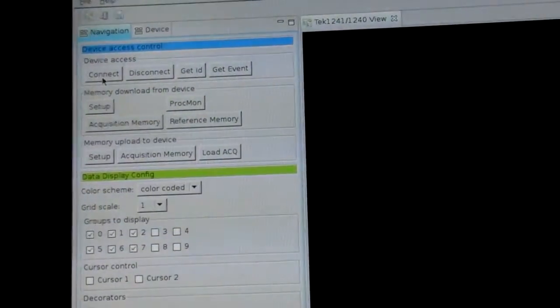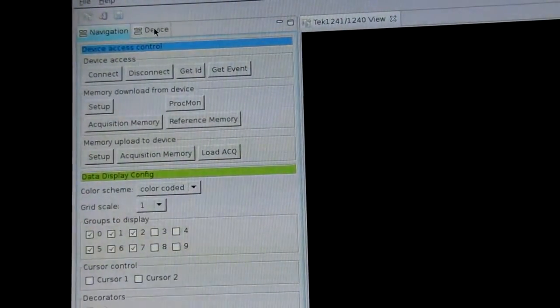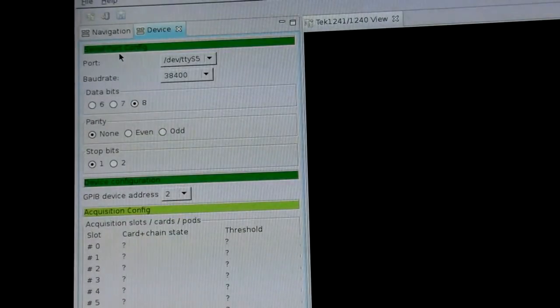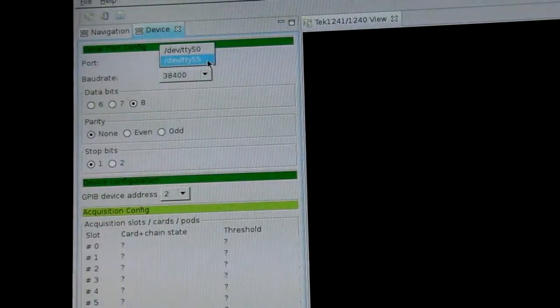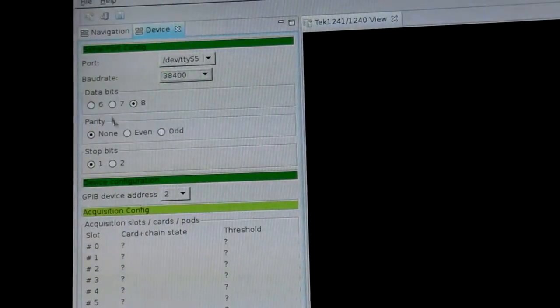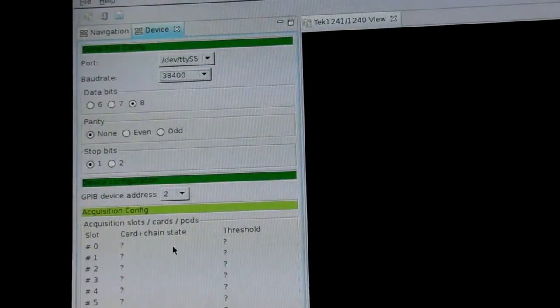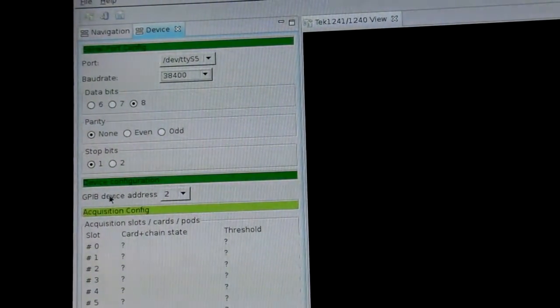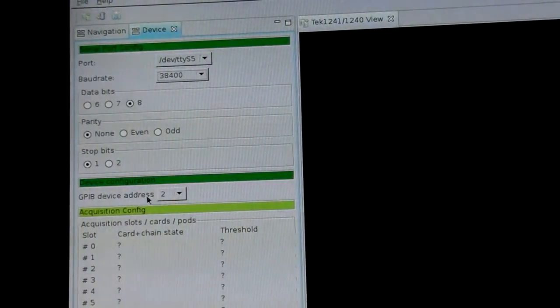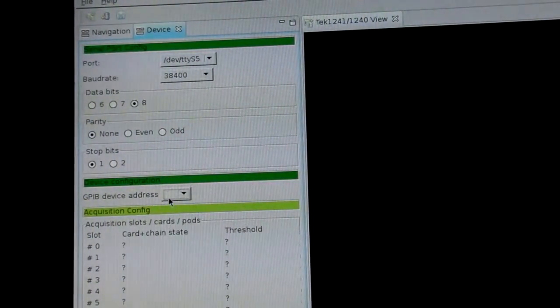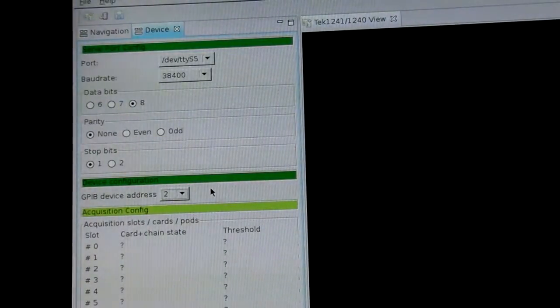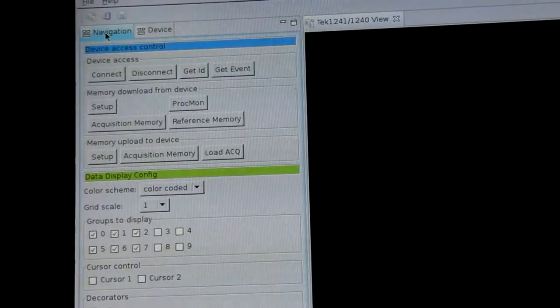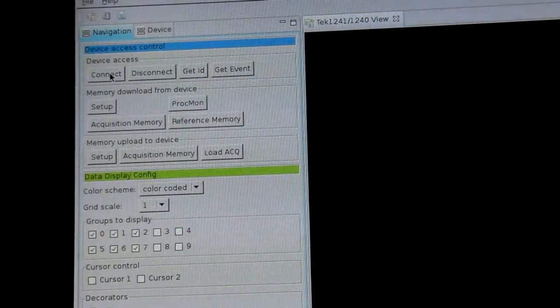And this is how it comes up. There is a big viewing area for the acquisition data which is empty so far. It's possible to have some basic configuration here. I move to the device tab where I can put in some serial port configuration like which is the port here, the baud rate and data bit parity and such things. And the GPIB device address we like to communicate with. So it's 2 here because the default address of the 1241 is 2. Okay, I move back to the other tab. I already connected to the device.